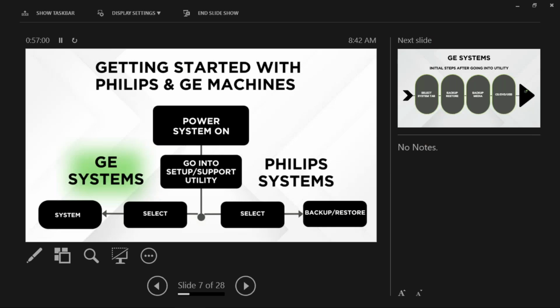One thing that will eliminate that is the presets on the system, right? So if you're clicking on the C51 transducer, right, click on the C51 transducer, then click the abdominal general preset, it will go back to that every time, right? So that's a default preset set by Philips, right? So I can always go back to that preset, or just one of the default ones. You don't want to go to a custom abdominal general preset named after a person. You want to make sure you go to the Philips preset ones. Those don't change unless they've changed them. And if they make a change to those, it won't allow you to change the default presets, right? So you'll have to add the person's name as that particular preset. So that's how you know if it's the default one or not.